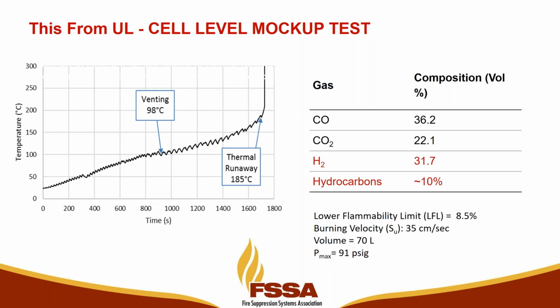Would CO2 be an option for suppression? I find that an interesting option, though there hasn't been any testing on it yet. What makes it interesting is that you could continue to inert that atmosphere for hours at a time with a larger tank. But does it become cost prohibitive to put a 10-ton tank out on a site to protect a 30-foot container? It's not going to provide you any cooling. It will suppress it, but the batteries will probably continue to propagate depending upon their configuration. So I don't see it yet, and there really hasn't been any testing.